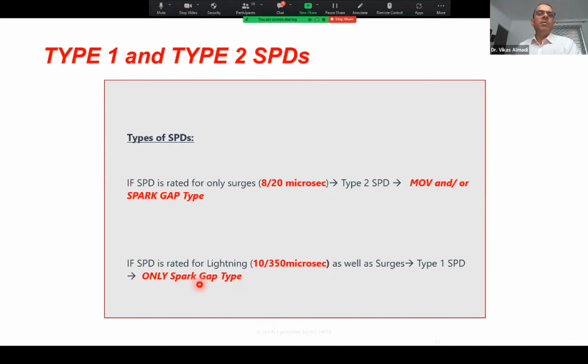So a spark gap is a kind of switch which creates a diversion path. Switch means short. Short means equipotential bonding. So for lightning purpose, a spark gap, and for surge purpose, which is a residual part, can be a MOV or can be again a spark gap. So spark gaps are used for both applications, whereas MOVs are used only for one application, in the ideal case.